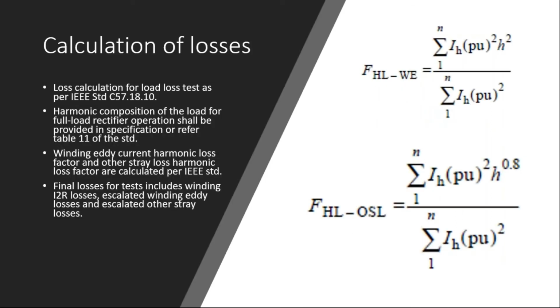Coming back again to the rectifier transformers, in these transformers the design is kind of complex when it comes to the loading and the harmonics requirement. The harmonics requirement is given in table 11 of the standard C57.18.10, and it gives you, for different pulse applications, the harmonic levels for different harmonic numbers. So for example, for a 6-pulse converter, you will have harmonics 5, 7, 11, 13, and so on.